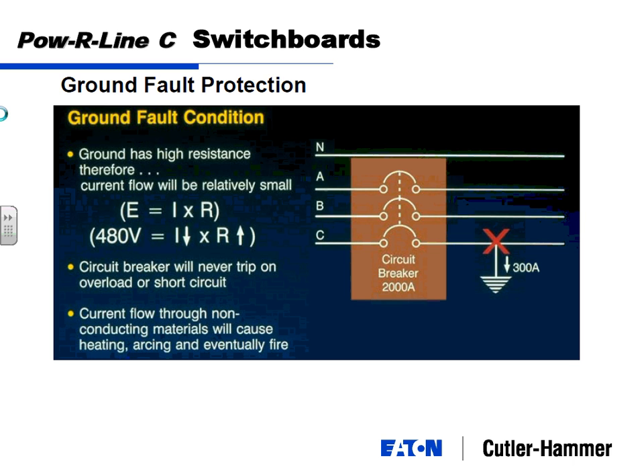you got a 2,000 amp breaker here and you get a ground fault anywhere on the load, so you could be down 2 levels of breakers even. Ground fault inherently is going to have a high resistance because it's not following a bus bar, it's not following a wire, it's finding some other way to escape from the cable. So it's going to inherently have a lower fault current value. In this case, 2,000 amp breaker, you've got a 300 amp ground fault, and that'll keep running and running and running.